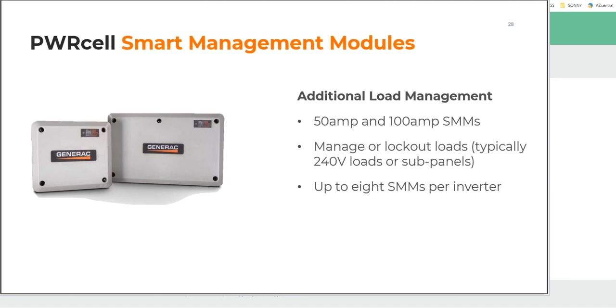This is a good representation of what these smart management modules enable you to do. Say we've got 85 amps of load that we want to put into a backup panel. We don't have to power them all at one time, but we do know we want to get power to all of it at some point during a blackout. If we were to set it up without any smart management modules, this is what it would look like in the service panel, according to code. This wouldn't pass inspection, so you wouldn't be able to sell this system to your customer, even if your customer agrees they're just going to turn some things on individually.